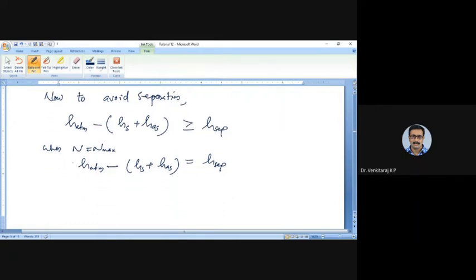Let us substitute: H ATM value given as 10.3 meters, minus suction head value, specified as 4 meter, no sorry, 3.5 meter, plus HAS, which is 0.3185 omega square, equal to H separation value, 3 meters, so this is equal to 3.